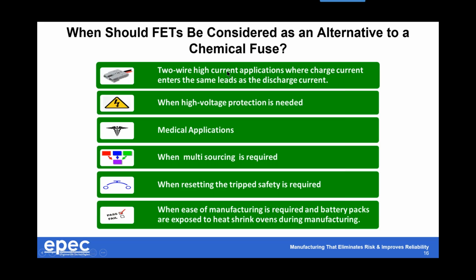One application: say you have a 2-wire system, with a couple small current paths for fuel gauge and communication, but all your charge current goes through 2 wires and all your discharge current goes through 2 wires. That's a lot of current. Most chemical fuses can't handle high current, hundreds of amps. They just don't exist. That's where FETs really shine.